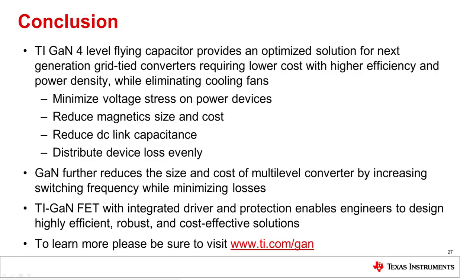The four-level flying capacitor topology utilizing TI's LMG3410R050 GaN device is an optimized solution for next-generation grid tie converters, providing low cost, high efficiency, and high power density while eliminating cooling fans. The topology reduces voltage across power devices and filters to one-third of the DC bus voltage, enabling high-efficiency 600-volt GaN devices and reducing the size of both the power inductor and EMI filter. The topology evenly distributes heat across power devices to simplify cooling, and GaN's high switching frequency further reduces filter components to improve power density while maintaining high efficiency. TI GaN FETs with integrated driver and protection enable efficient, robust, and cost-effective power solutions.